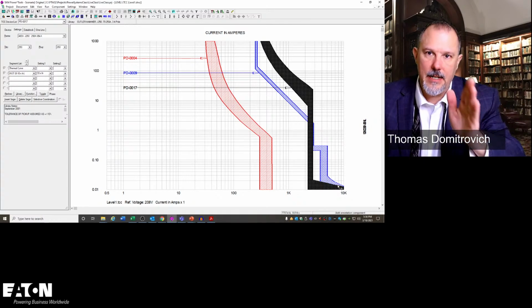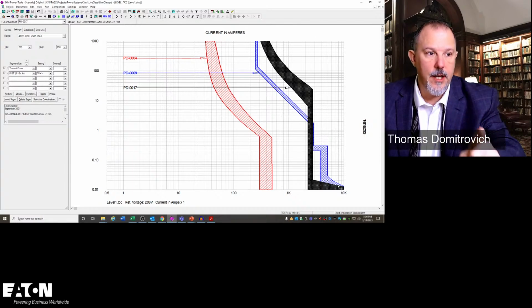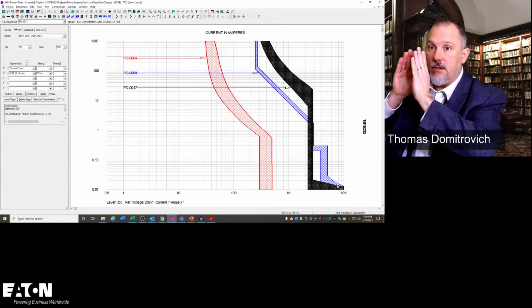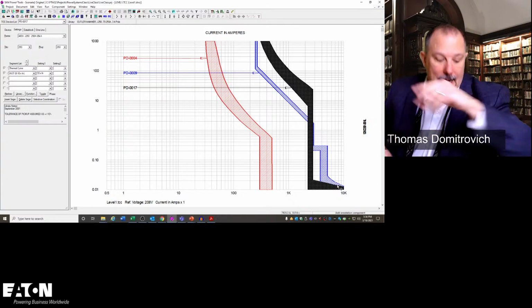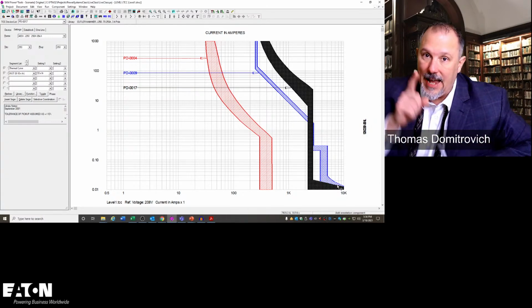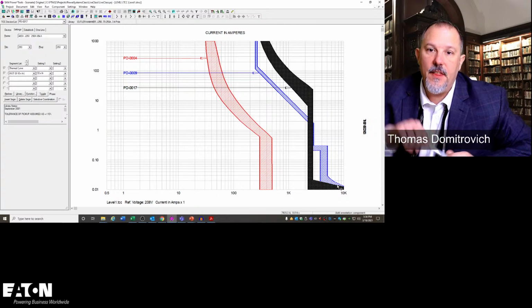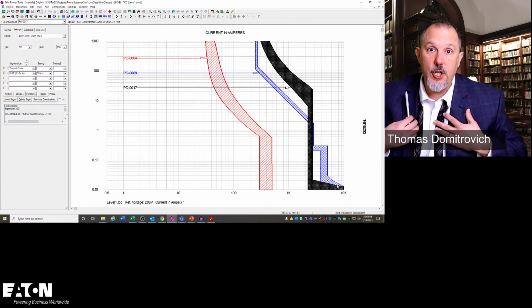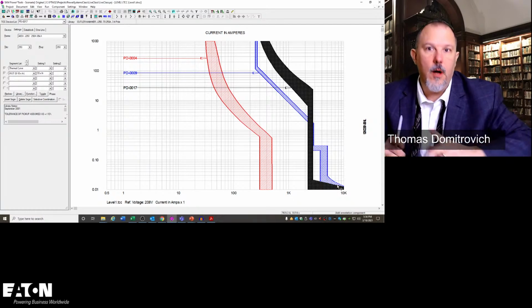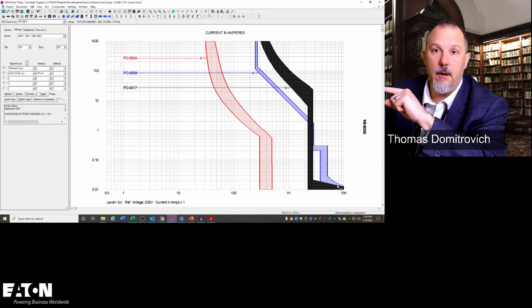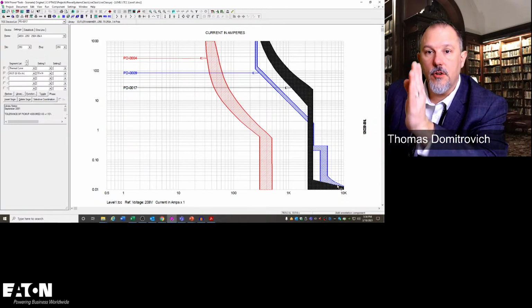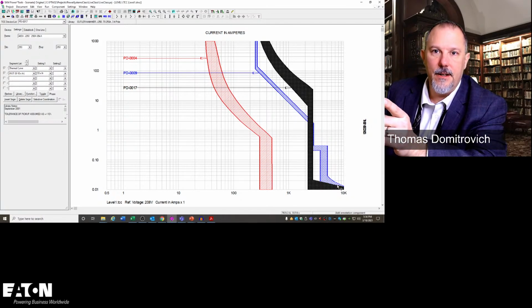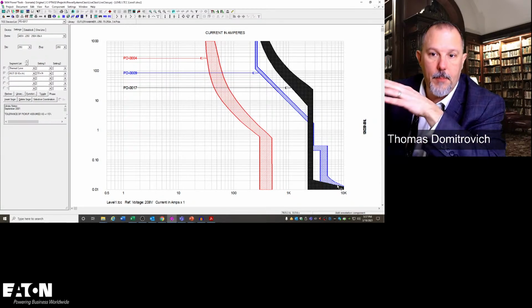I'm into the instantaneous region of both circuit breakers. Based on this TCC curve, I would have to make a determination at the available bolted fault current that they do not selectively coordinate. What I can ascertain from the trip curves, because the fault current is greater than the instantaneous pickup of both of those devices, is that the likelihood is there that based on the information available, they're both going to open, based upon this information, the TCC curve.